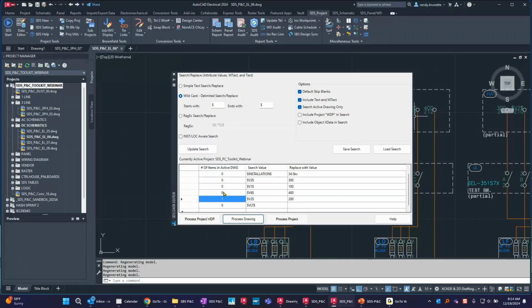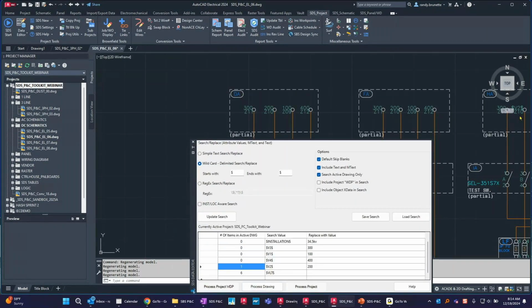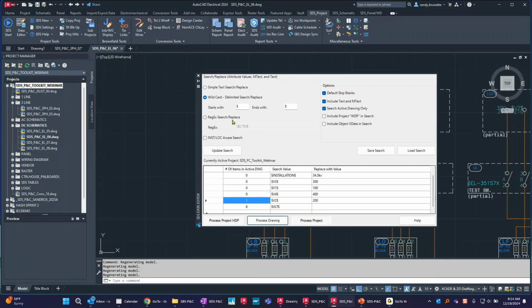Notice these are all marked as 0. This one has 1 because we missed one of them. And if we look at the drawing file, here are all those values that were filled in, and here's the one, SV25, that we ignored from our listing. So imagine doing that manually as you brought in a standard and had to manually edit 104 different pieces on each one of those components. You can see how this could easily take, and this comes from one of our customers, actually the one that requested this tool, their time for creating a new substation based on standards from 3 weeks to 3 days. So pretty phenomenal savings with this tool.